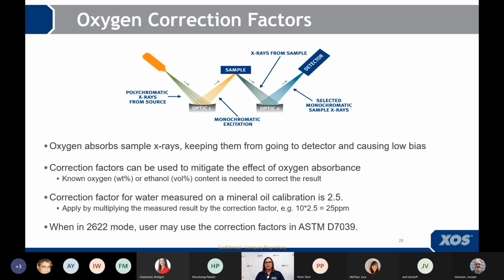The last thing to note is that if you have a Sindie 2622 and you're in 2622 mode, you can use the correction factors in 7039 even though you're running 2622. This is because the basic analyzer geometry hasn't changed between modes. You're just running a background measurement. So those correction factors in 7039 would be applicable for 2622.